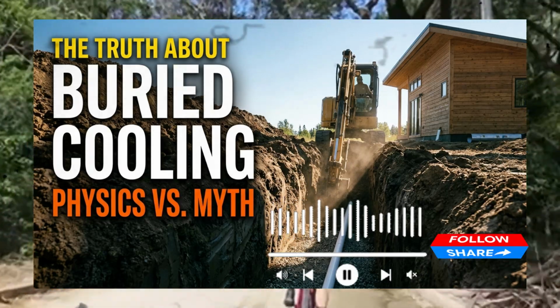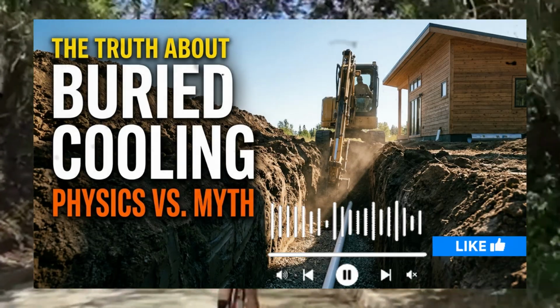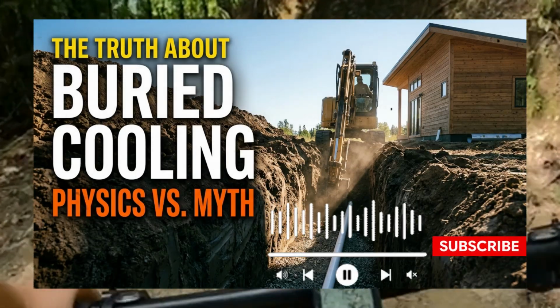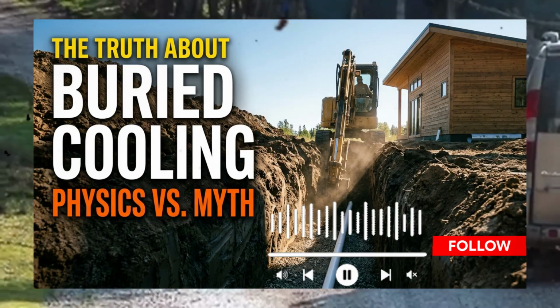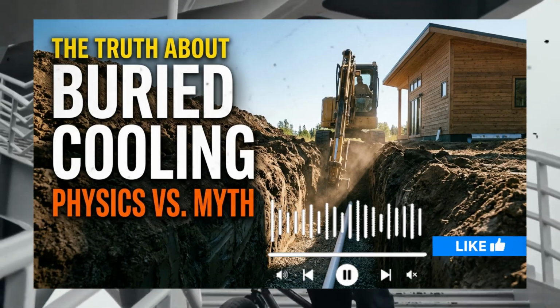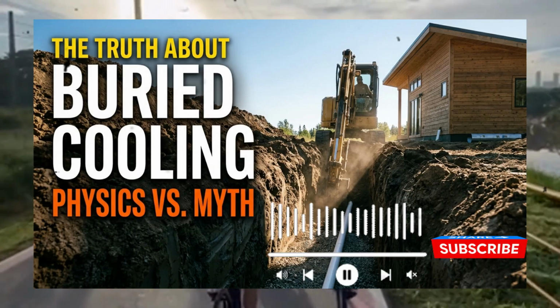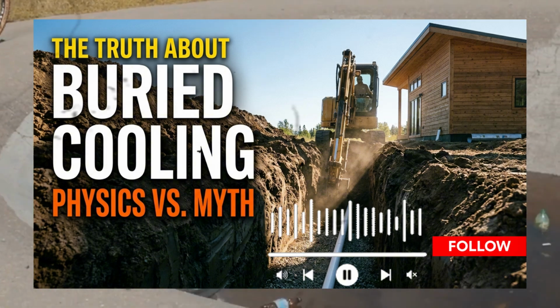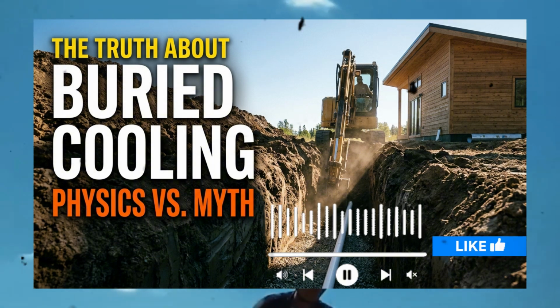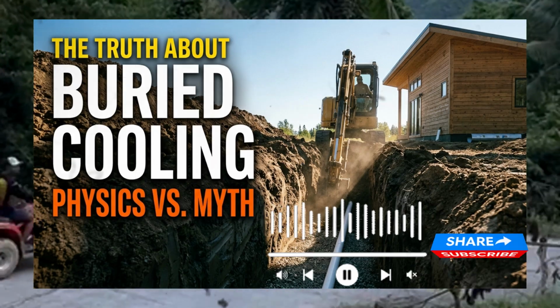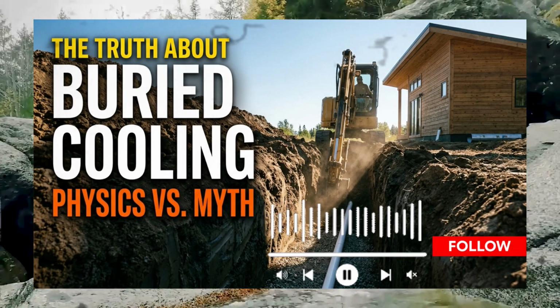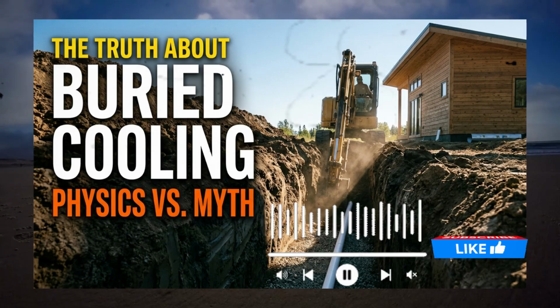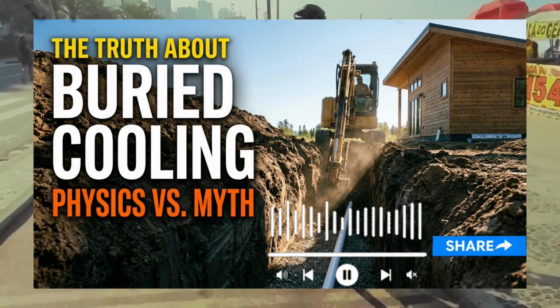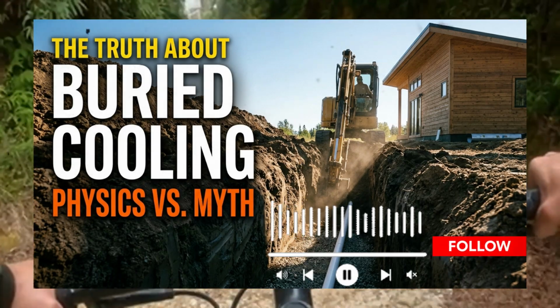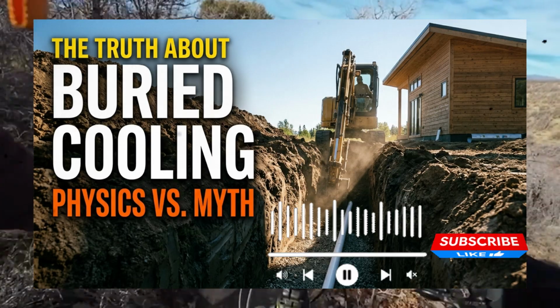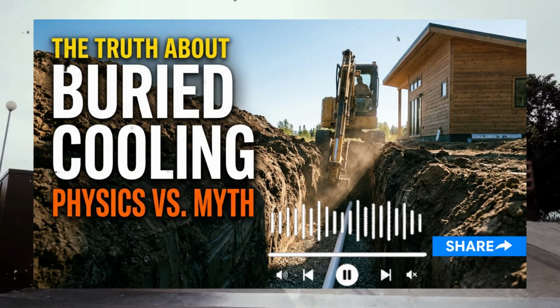Conversely, if you move the air too slowly, the air cools down quickly, but the overall volume of air delivered to your home is too small to overcome the ambient heat gains of the structure. To find the perfect thermodynamic sweet spot, we must maintain a laminar to transitional flow velocity of exactly 400 to 600 feet per minute. At this speed, the air is moving fast enough to provide a high volume of fresh air, yet slow enough to allow the thermal energy to thoroughly conduct through the boundary layer and into the soil.